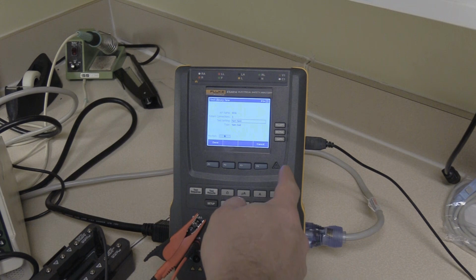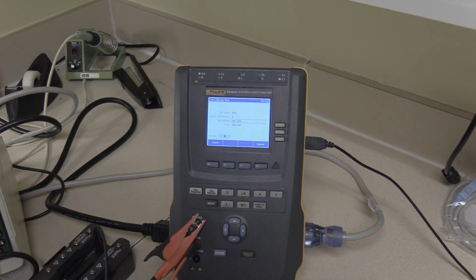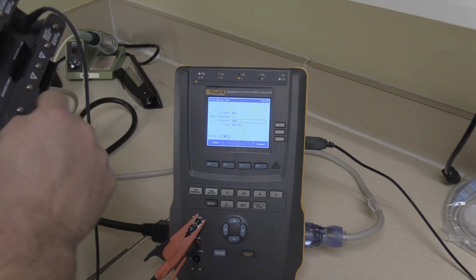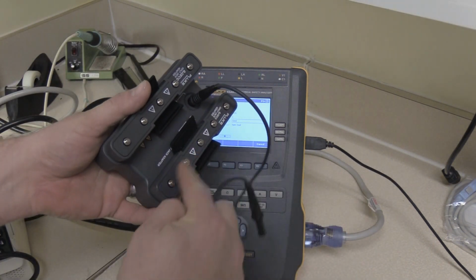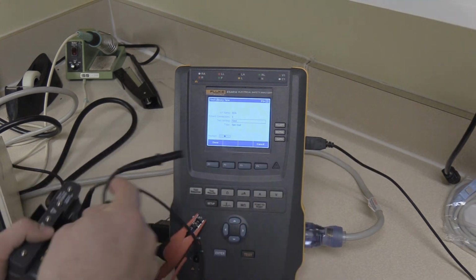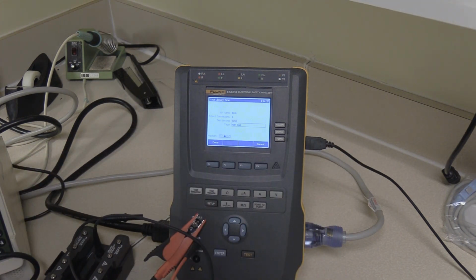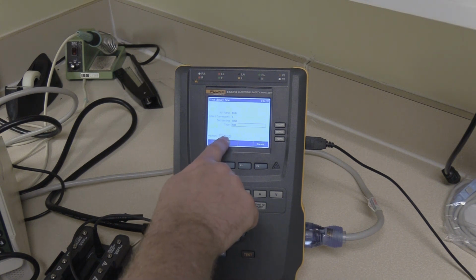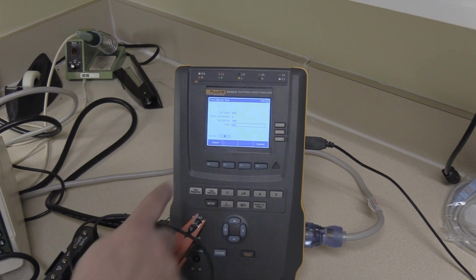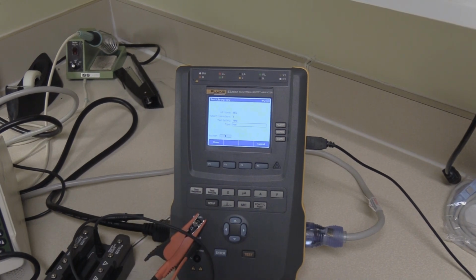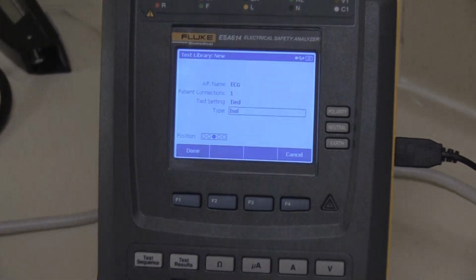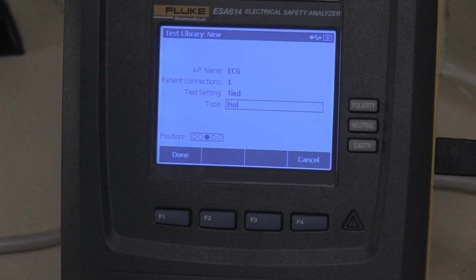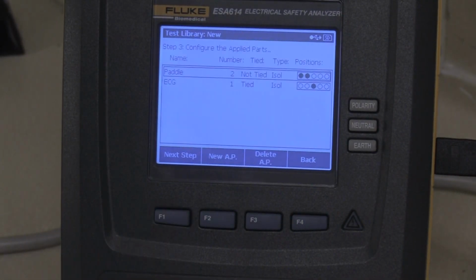And where it says setting not tied, since we're going to go through the block, they're all averaged together, so we're going to change that to tied. Since they're all tied together, all the results will be coming out of 1 cable. And then also, since it's a defibrillator, these will be isolated like it was in the original setup. And you can see which position is going to be assigned to it. Those positions correspond to the holes on the top of the ESA614. There's a better view of it, and we're going to select done.